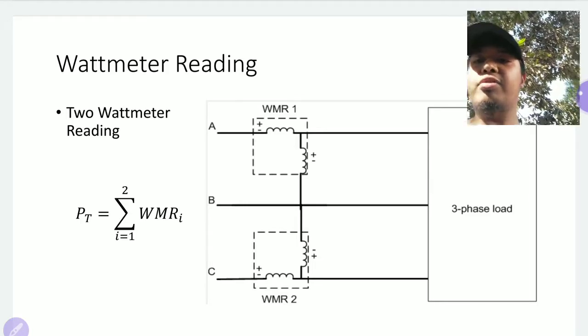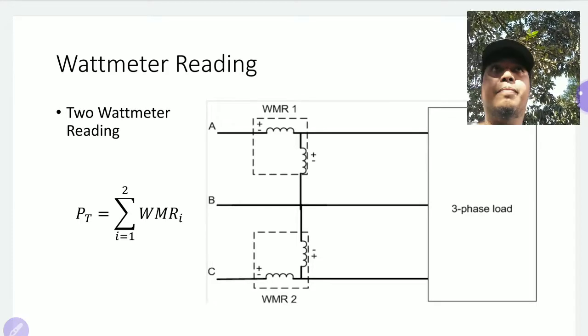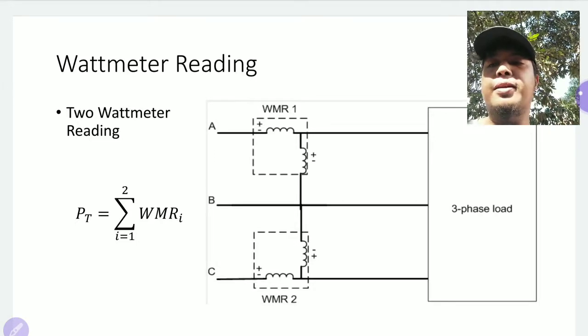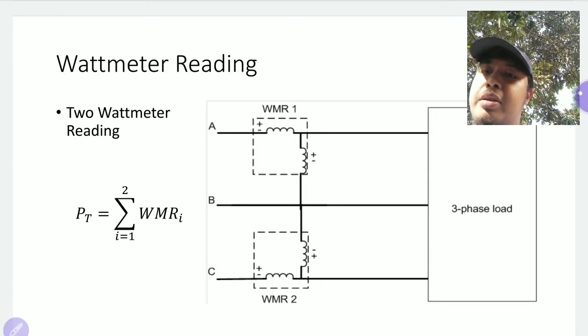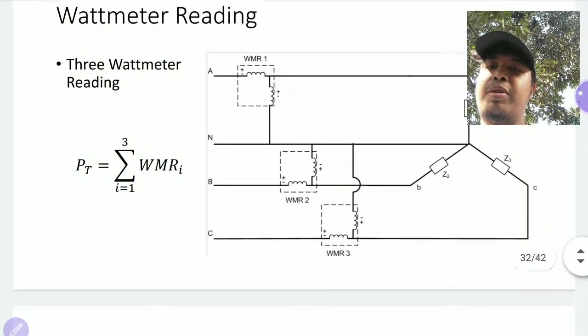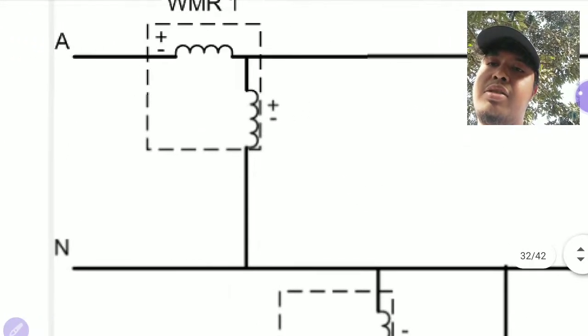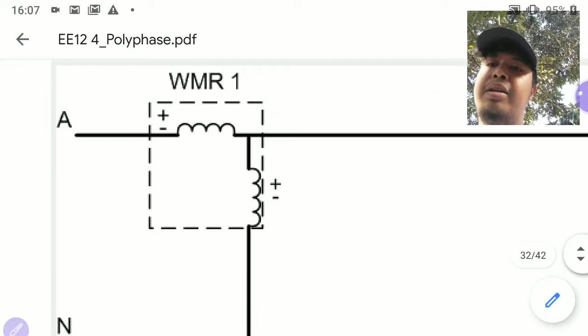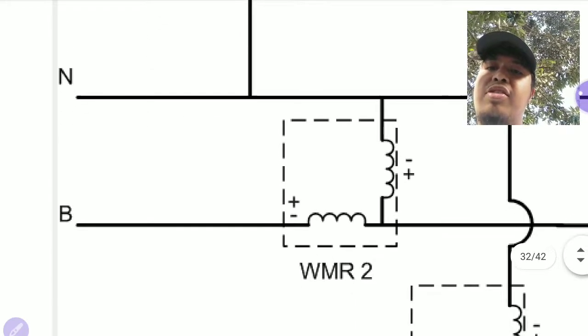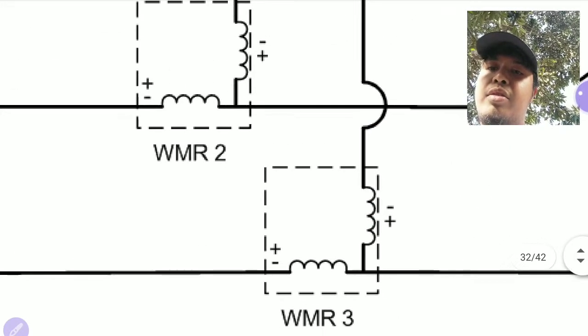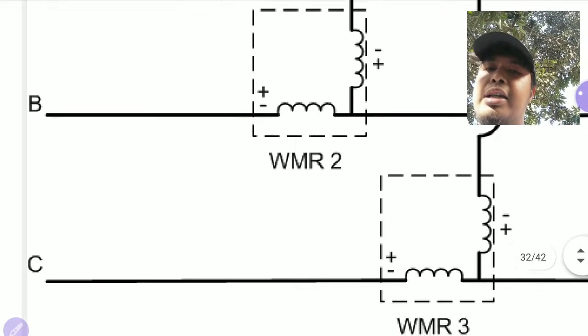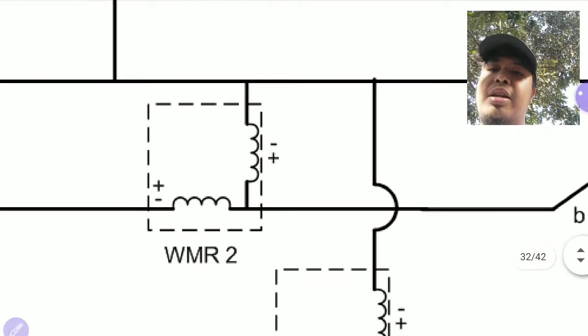Just like any other system, power is always additive, so for the two-watt-meter method you simply add the readings of the two watt meters to get total power. What's important to note when comparing the two-watt-meter method to the three-watt-meter method is that for three watt meters you have the voltage from line to neutral, with the line being at higher potential than the neutral, and this is the same for all lines — line B is higher than neutral, and line C is higher than neutral.